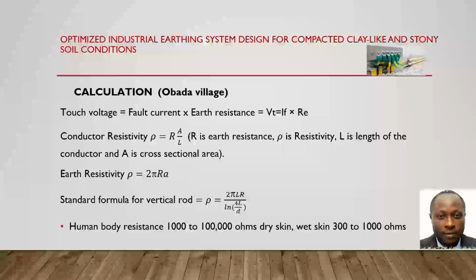Now, I need everyone to pay attention. Though the meter will tell us the resistance direct, and you can use that resistance to know where you are, in calculation people can make mistakes in resistivity. The calculation for conductor resistivity is different from the calculation used for earth resistivity. So you need to know that very well.